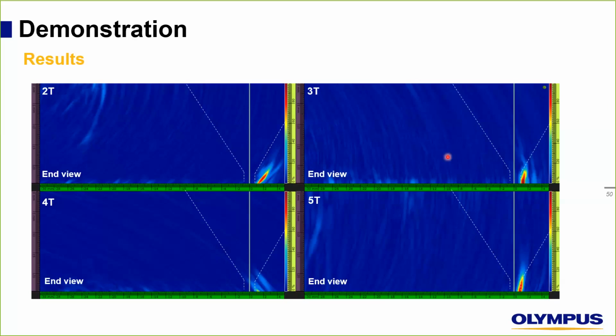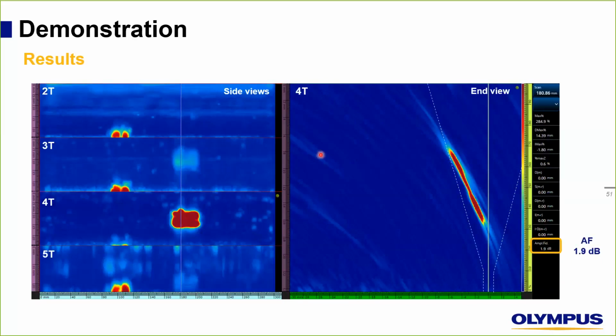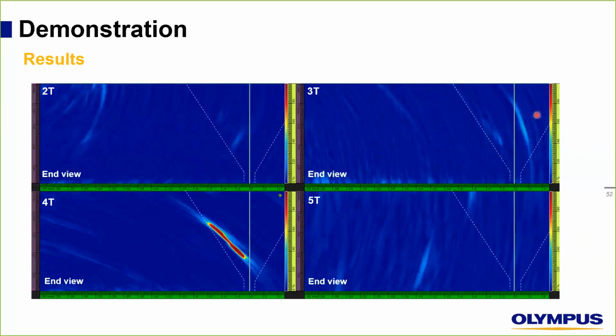Let's have a look at the second defect, or second flaw, which was a lack of fusion. We clearly see that only one group detected this type of flaw well. It's the 4T, and it's normal since it's like standard phased array. This is the best way to detect such flaw orientation. For 2T and 5T, we see nothing, a little noise, but nothing really important. In 3T, we still see some indication, but we will see here that there is an offset between the real position of the lack of fusion and the position shown on the 3T.